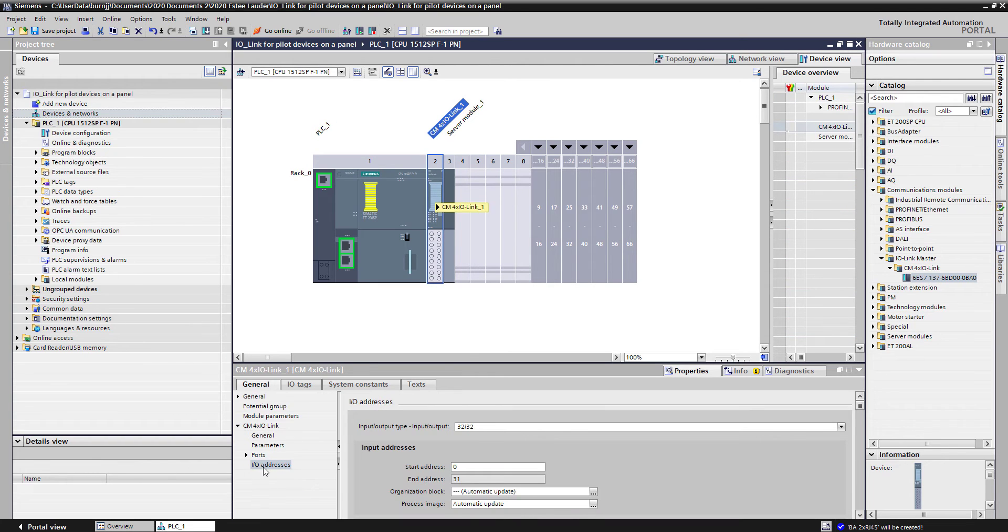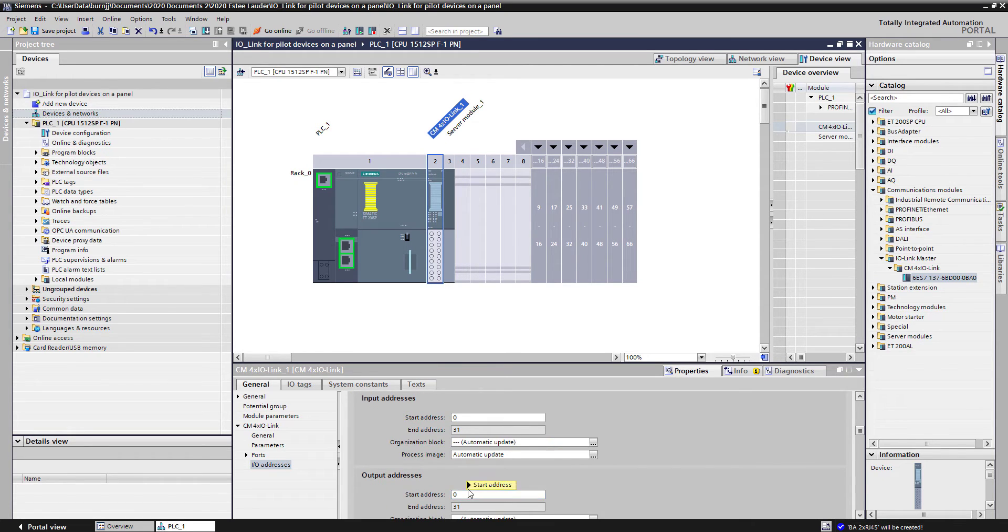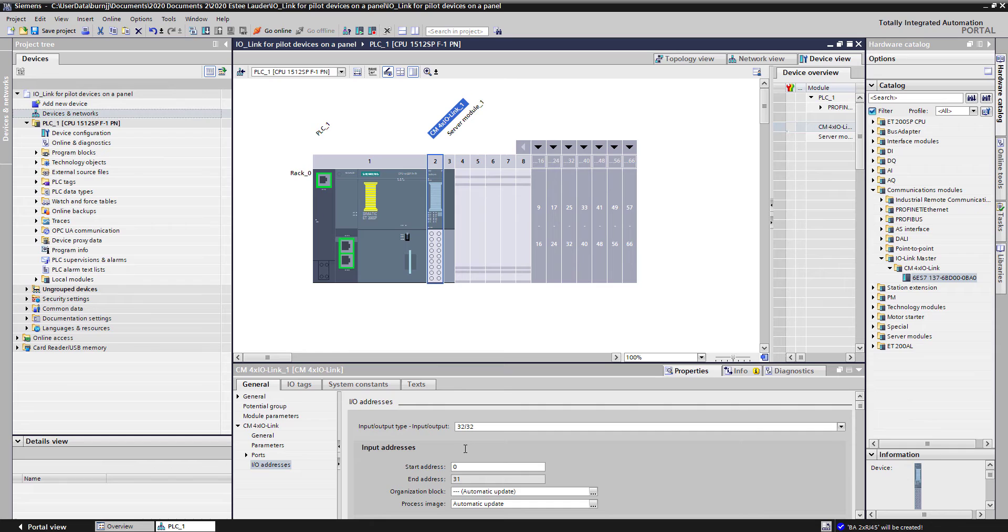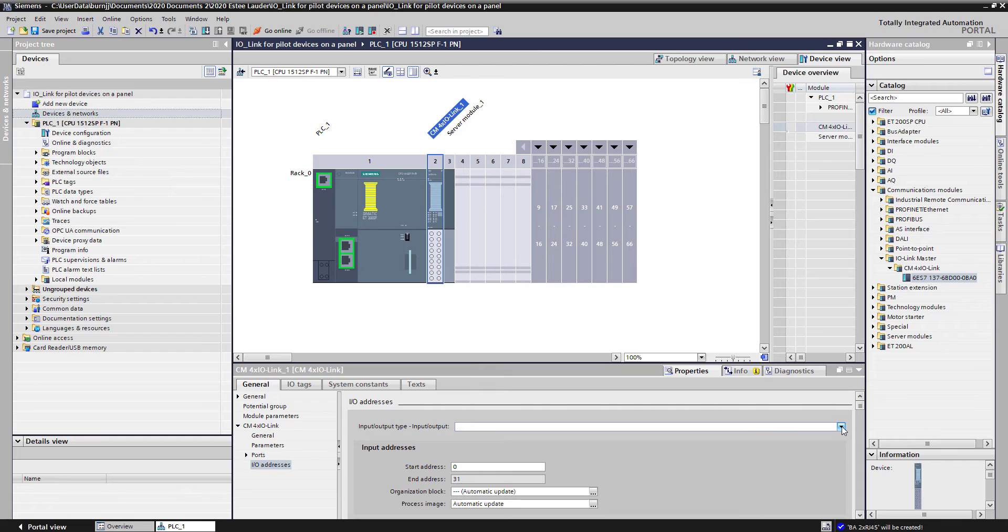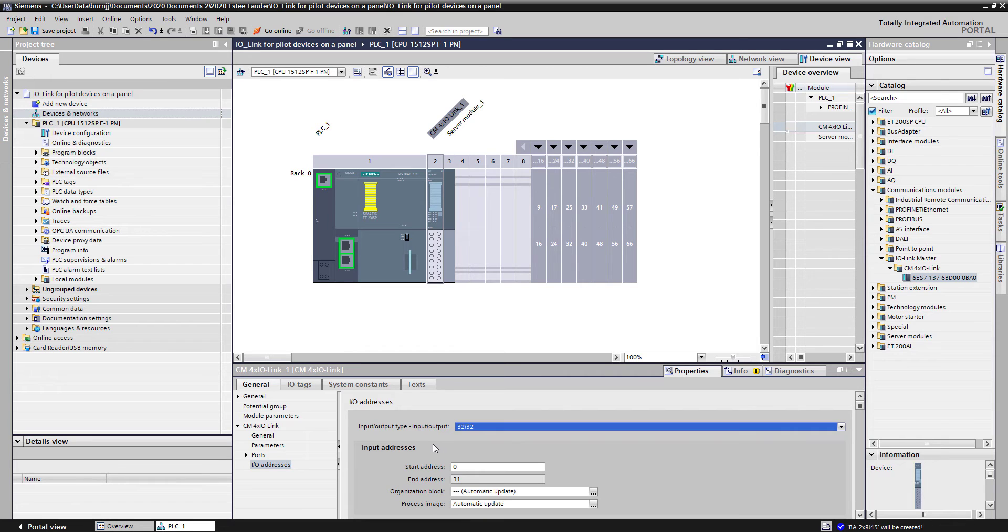Once I did, if you look, I've already assigned IO addresses starting at bit 0 for the input and bit 0 for the output, and it was a field size of 32 bytes in, 32 bytes out that got reserved. If you know your IO-Link devices won't consume that many bytes, you can reserve less IO space. I just usually take the default 32 and 32 for my systems.